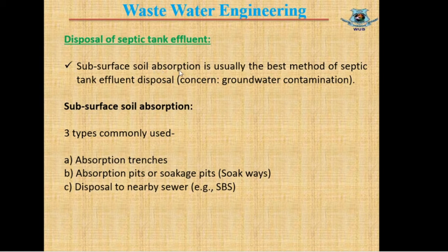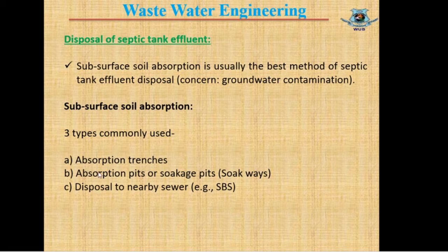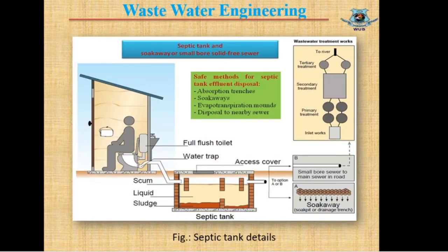Septic tank effluent can be disposed of into subsurface soil absorption, which is usually the best method. Subsurface absorption means restoring the effluent into the soil from a reasonable distance from the groundwater table to prevent groundwater contamination. There are three types: absorption trenches, absorption pits (or soak pits, common in our countries), and disposal to a nearby sewer system, commonly known as the SBS system.